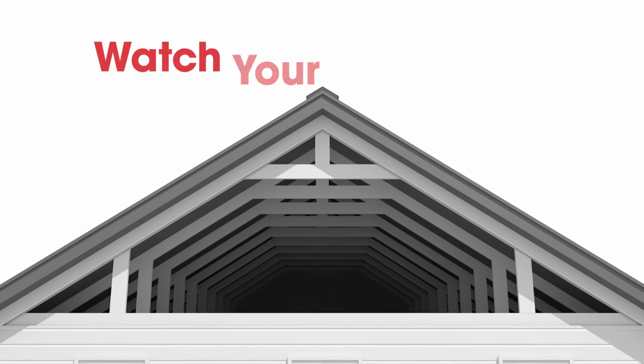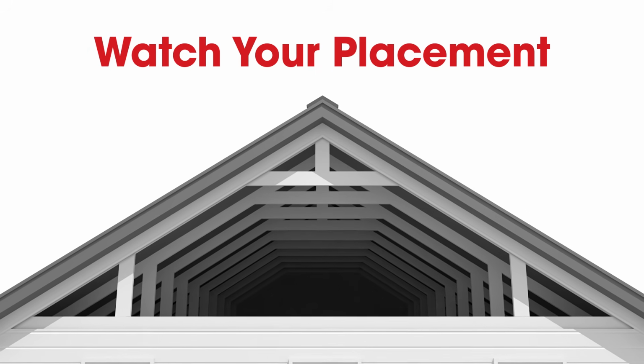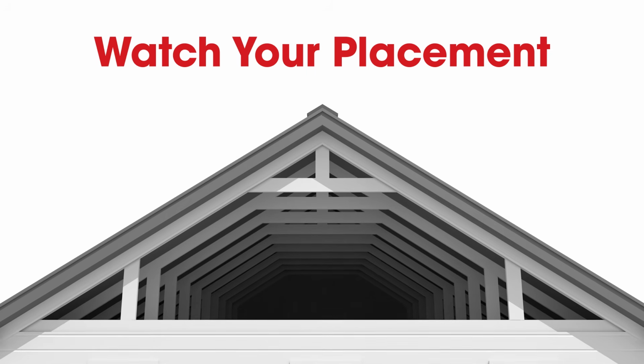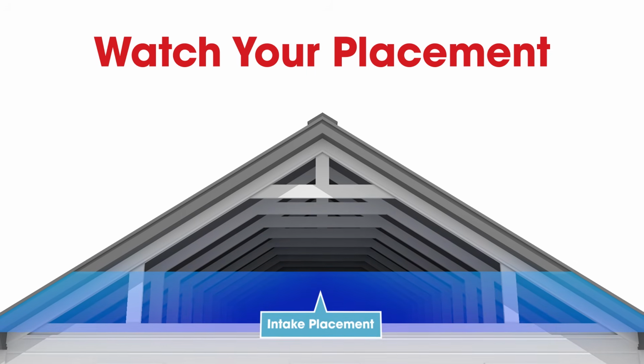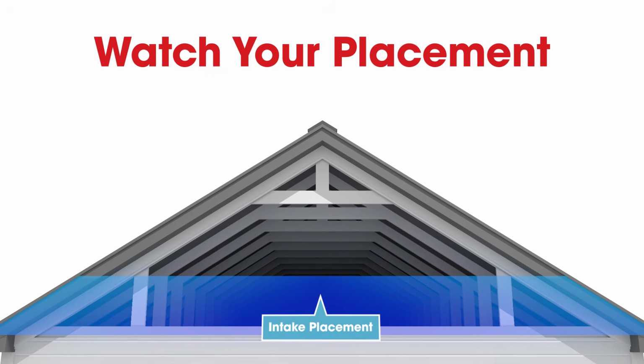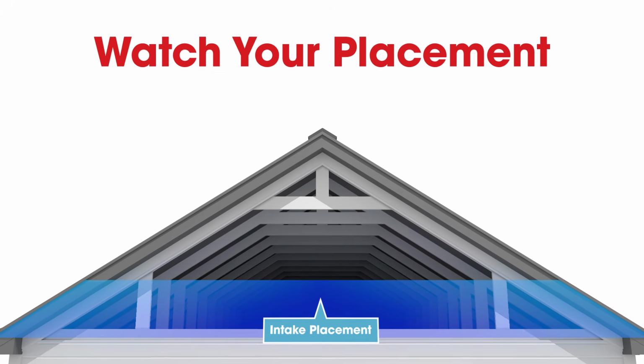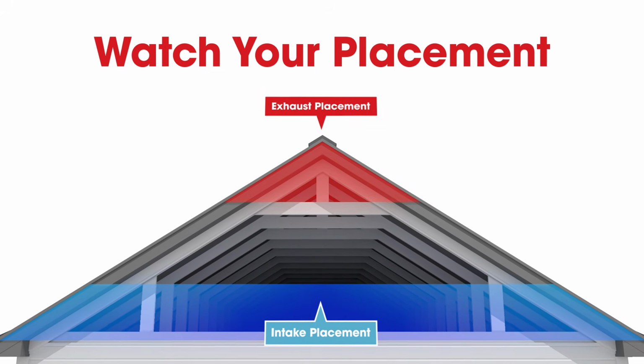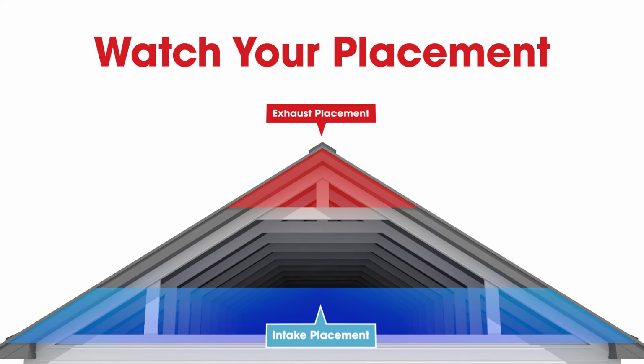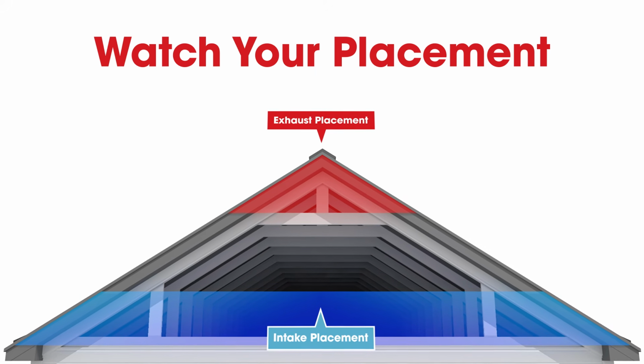The last principle is to watch your placement. For a system to function properly, intake needs to be located at the lowest part of the attic space, on the roof. This is typically at or near the soffit. Likewise, exhaust should be located at the highest part of the attic space, typically at or near the ridge of the roof.